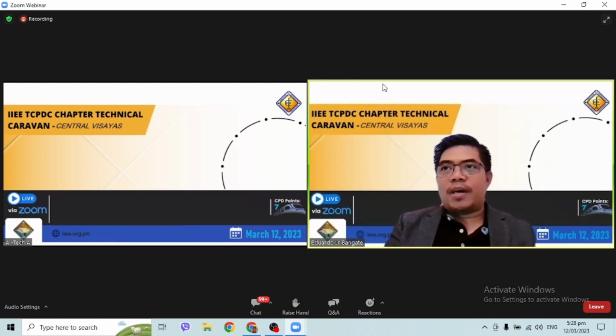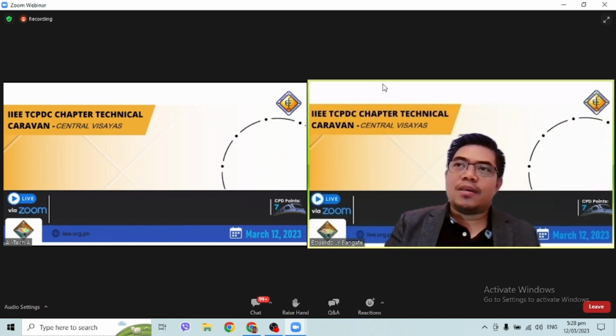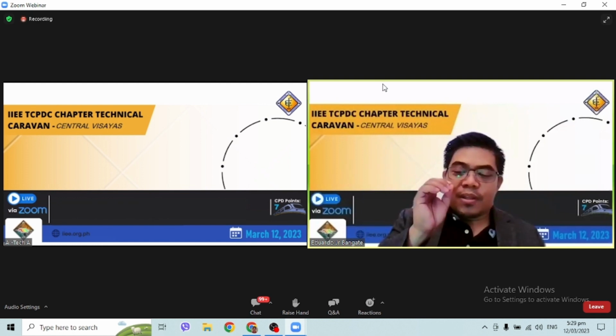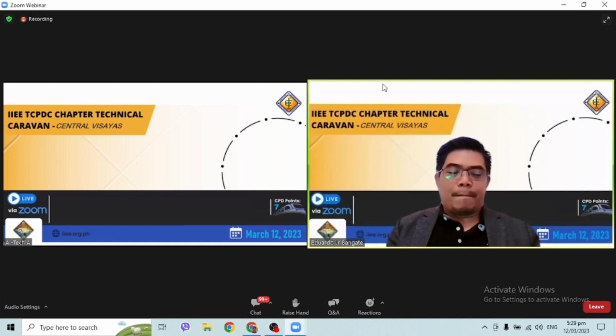So, pero yung sinasabi natin na okay lang ba na isa lang, na may big load, again, the optimum level is 70 to 80%, but if you have a motor load, you can never start your motor with a single generator. Okay, take note of that.